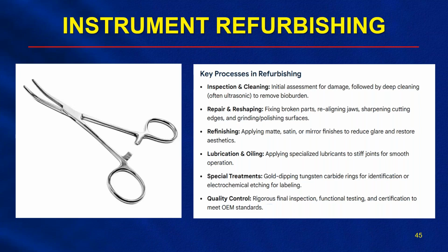Now, the key processes in refurbishing include inspection and cleaning. That's the initial assessment of damage, followed by deep cleaning, usually ultrasonic, to remove bioburden. Repair and reshaping: they have the ability to fix broken parts, realign jaws, sharpen cutting edges, and grind and polish surfaces. And then refinishing, applying matte, satin, or mirror finishes to reduce glare and restore aesthetics.